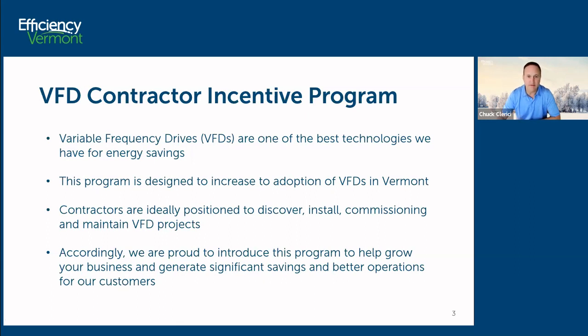Pound for pound, I've always said VFDs are one of the best technologies we have for energy savings. The reason for that is that there are a lot of pumps and fans out there. These are centrifugal loads that when you slow them down even a little bit, the savings is cubic because of something called the affinity laws. When you slow a centrifugal motor down 10%, you save 25% in energy. When you slow it down 20%, you can save 50% in energy. So this is very high impact technology.